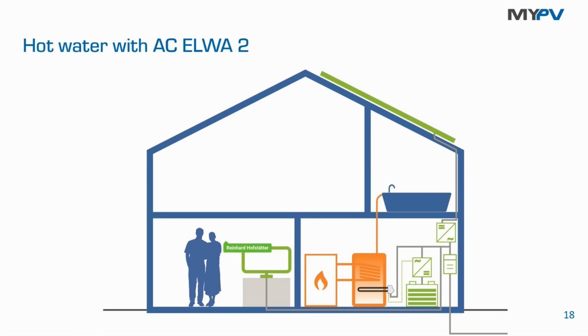And what we make use of is just the surplus. It's just the excessive power. It's just the energy that would be fed back into the power grid. And to detect this surplus, it needs a metering in the feed-in point next to the utility meter of the energy supplier. And this is the place where the IME meter is installed. It's then giving us the excess power information to an AC ELWA 2 or an actor via an RS485 communication. So it's Modbus RTU that we are using to communicate with an IME meter. And when you just switch on the light in the living room here, we immediately reduce the power output on the heater, because it's just about the excessive power. It's just about the balance in the feed-in point.